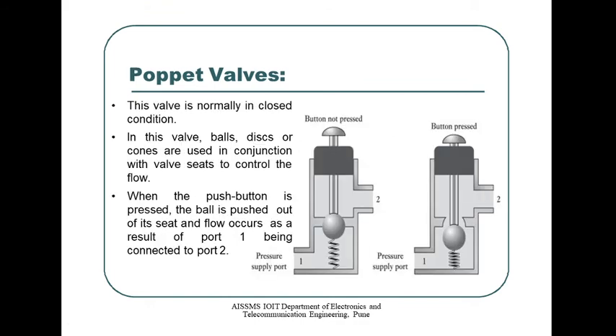These are the construction symbol and the graphical symbol of a 2/2 poppet valve. Let's understand the poppet valve operation. This valve is normally in a closed condition. In this valve, the ball, discs, or cones are used in conjunction with the valve seats to control the flow. When the push button is actuated, the ball is pushed out of its seat and the flow occurs; as a result, port 1 is connected to port 2.